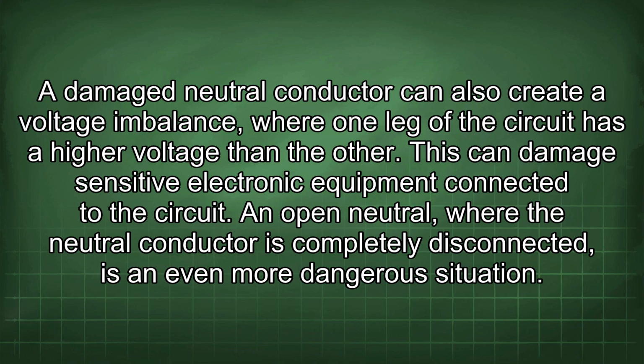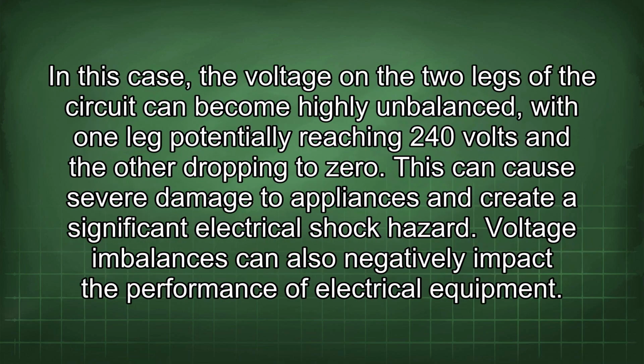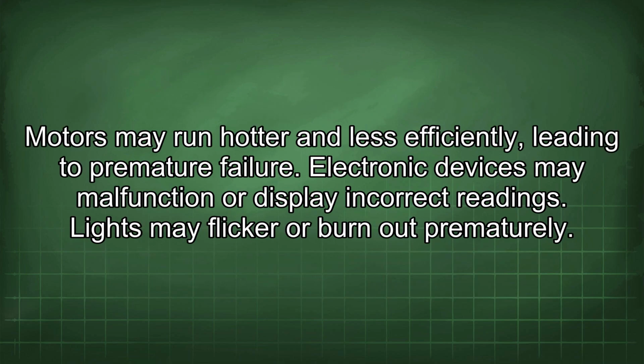An open neutral, where the neutral conductor is completely disconnected, is an even more dangerous situation. In this case, the voltage on the two legs of the circuit can become highly unbalanced, with one leg potentially reaching 240 volts and the other dropping to zero. This can cause severe damage to appliances and create a significant electrical shock hazard. Voltage imbalances can also negatively impact the performance of electrical equipment. Motors may run hotter and less efficiently, leading to premature failure. Electronic devices may malfunction or display incorrect readings. Lights may flicker or burn out prematurely.